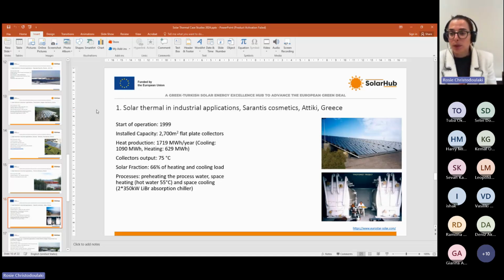The collectors can produce heat at a temperature of 75 degrees. And as I said earlier, this heat is distributed either to a cooling loop or to a heating loop. So this solar thermal system is used for the preheating of the process water, for space heating in the form of hot water at 55 degrees Celsius, and for space cooling and refrigeration via two absorption chillers, each one having a cooling capacity of 350 kilowatts.